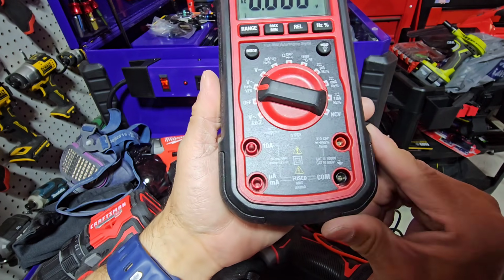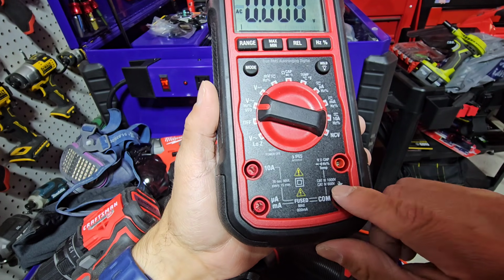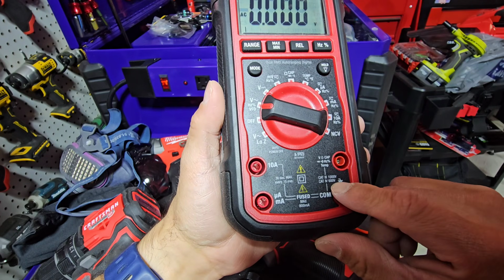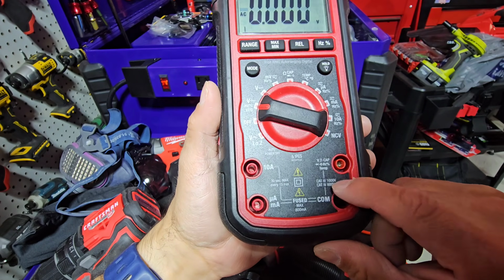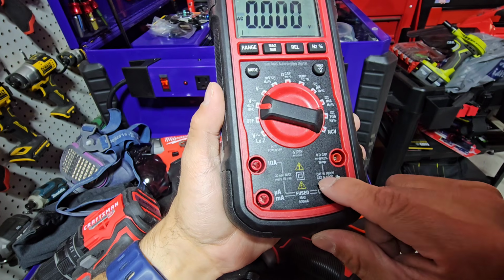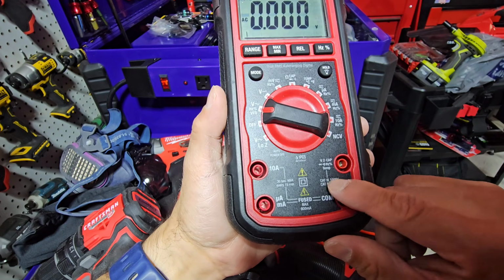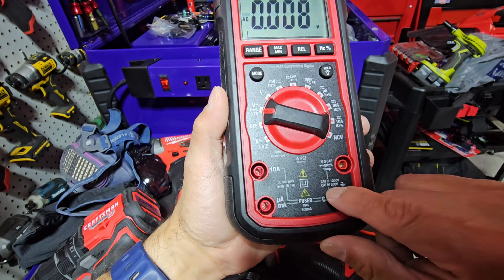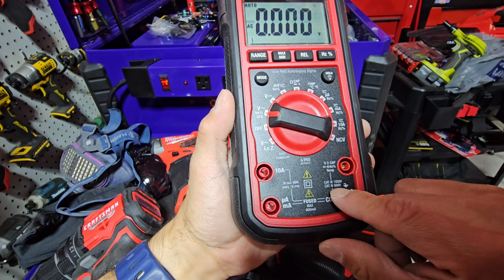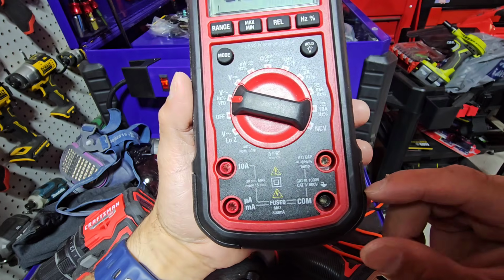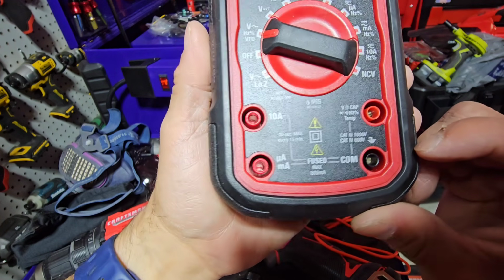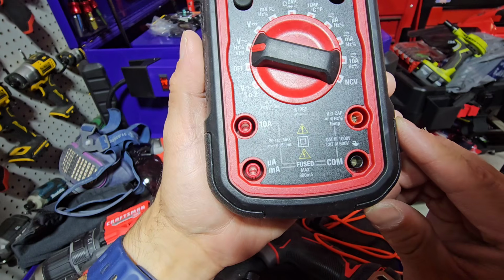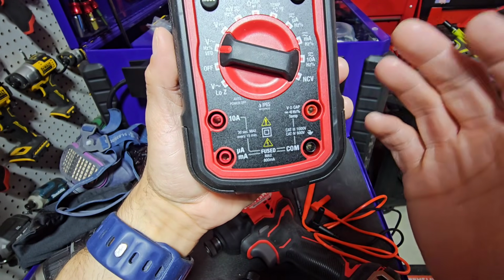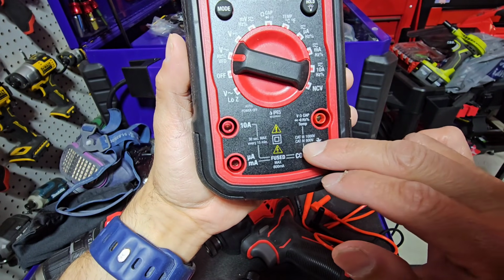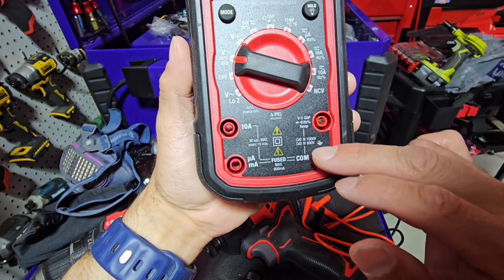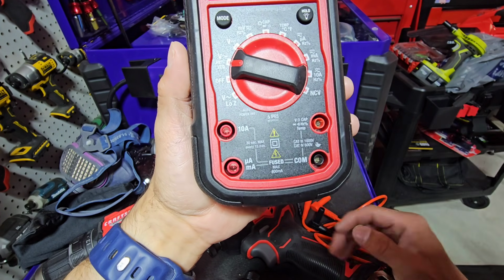They might have the Cat 4 1000, but it doesn't matter. In this case, you have Cat 4 up to 600, so you can use this outside up to 600 volts, and the Cat 3 is rated for 1000 volts, which is excellent for indoors. If your meter is only rated up to Cat 3, I'd advise not to use it outside. But Cat 4, as long as it's got that rating, is fine for pretty much residential use. You can use it in some commercial aspects too, depending on the type of commercial work, like HVAC or whatever. I'd recommend the Cat 4, 600 volts or under, for those types of jobs.